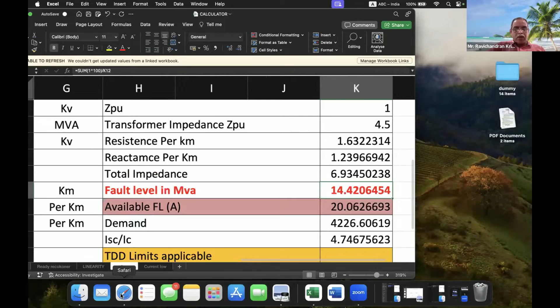From this, I am going to calculate the resonance frequency here. 14 MVA is the fault level. I chose a free online calculator that is available on the website, which you can use if you know the fault level. So here I am installing a 600 kVAR capacitor. The result is 241. See this, 241 hertz. It is closer to the fifth order.